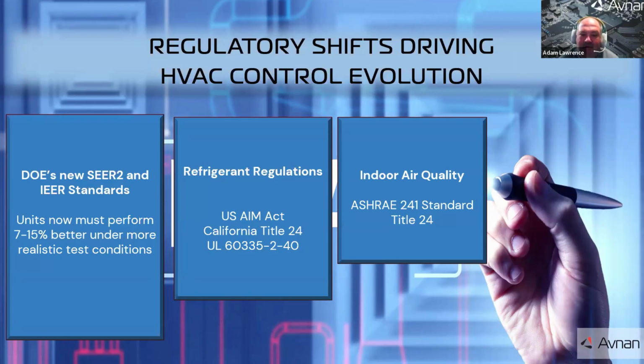Thirdly, indoor air quality codes. The ASHRAE 241 standard and updates to Title 24 require better ventilation control. Think demand-controlled ventilation based on CO2 sensors, occupancy, and IAQ feedback. Controllers must now modulate dampers and fan speeds dynamically, balancing air quality and energy use. These standards are already reshaping residential and commercial HVAC design.